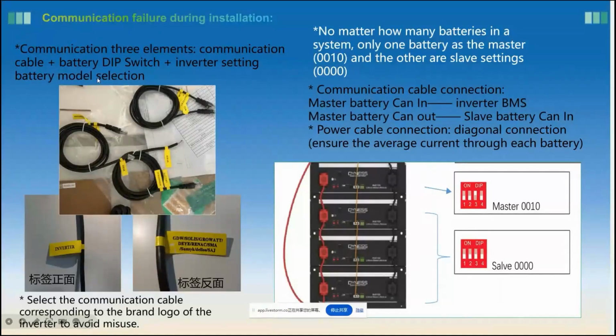For this whole system, with several batteries, we need to know that no matter how many batteries are connected in parallel in one system, there will only be one master battery. You can use this one as master, that's okay, or you can use this other one as master, that's also okay. The master BMS, the master battery, always connects to the inverter BMS port.